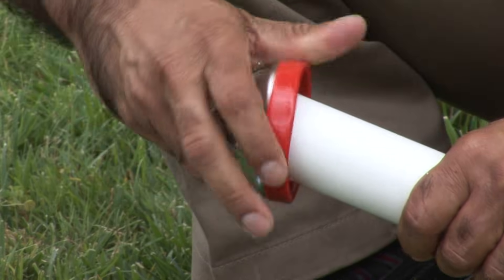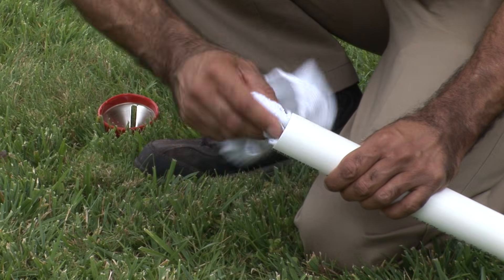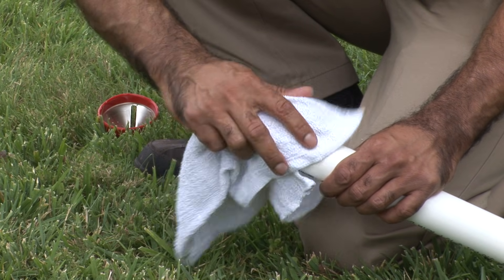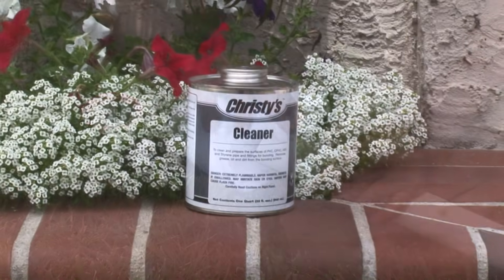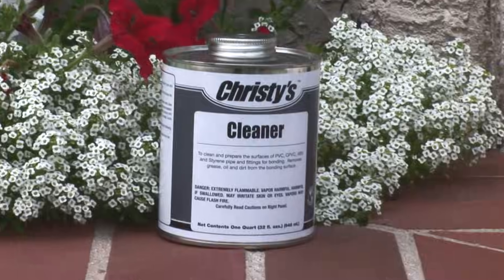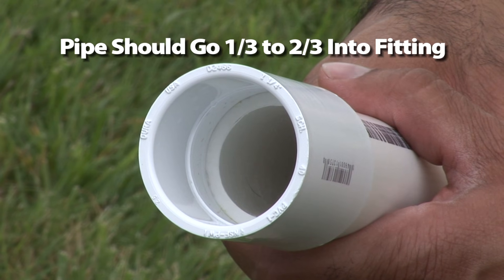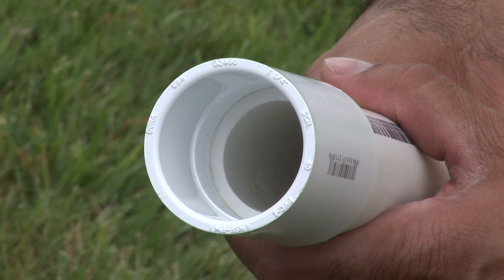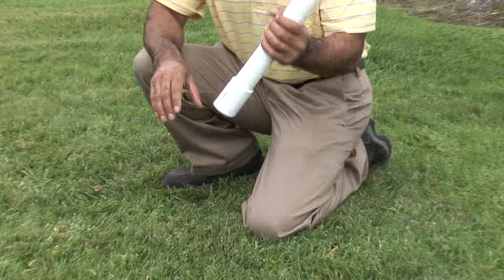You may need to use a file or beveling tool. Clean the joining surfaces of the pipe and fitting, making sure both are free of any foreign materials. To remove heavy buildup of dirt, grime, oil or grease you can use Christy's Cleaner. Test the fit of the clean pipe and fitting. Make sure it's snug. The pipe should go one-third to two-thirds into the fitting. The fitting should not be loose on the pipe or be able to fall off under its own weight.